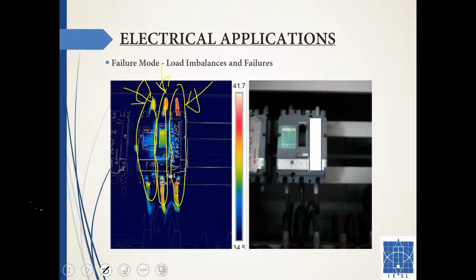Or one fine morning when you come to the office, you see these darkened cables. We don't know, because we do the survey at a given particular time - that's a snapshot, not a survey. The real deal happens throughout the day. You have fluctuating loads and varying processes, and you'll be cycling these bad connections throughout. So you need to pay attention to those.